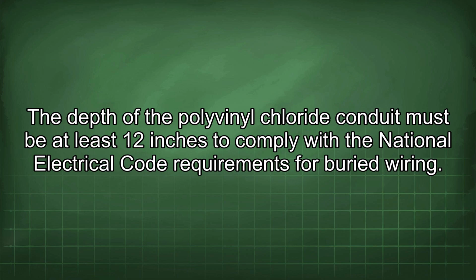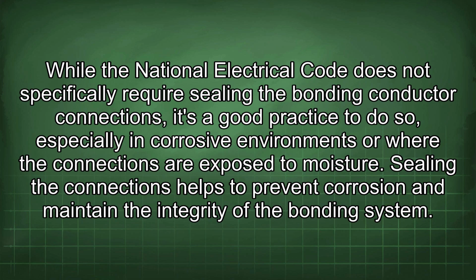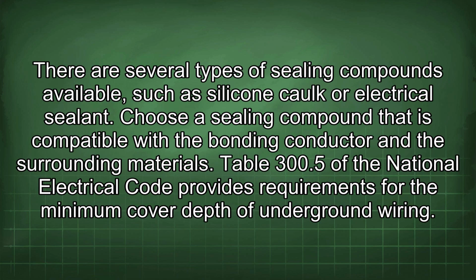requirements for buried wiring. While the National Electrical Code does not specifically require sealing the bonding conductor connections, it's a good practice to do so, especially in corrosive environments or where the connections are exposed to moisture. Sealing the connections helps to prevent corrosion and maintain the integrity of the bonding system. There are several types of sealing compounds available, such as silicone caulk or electrical sealant. Choose a sealing compound that is compatible with the bonding conductor and the surrounding materials.